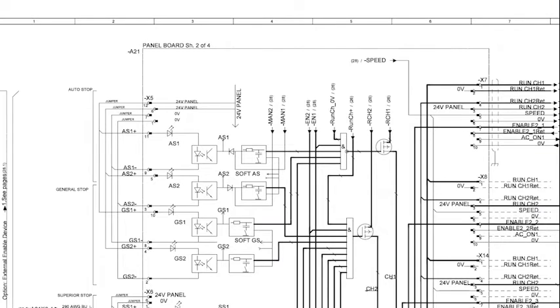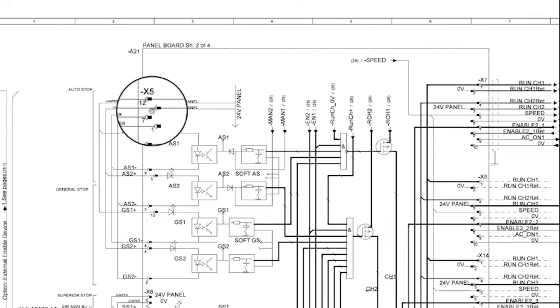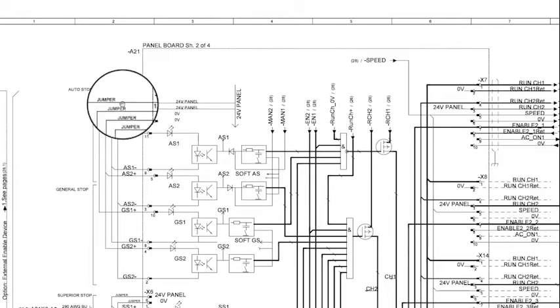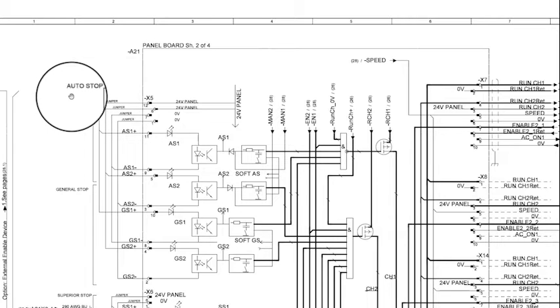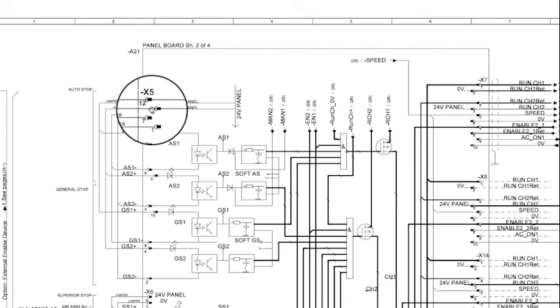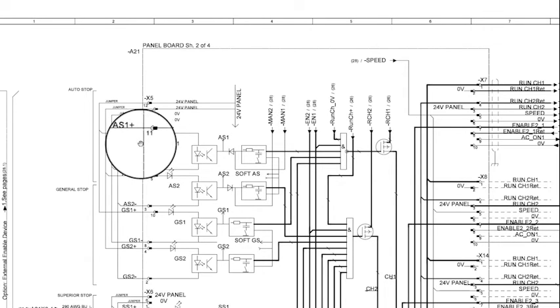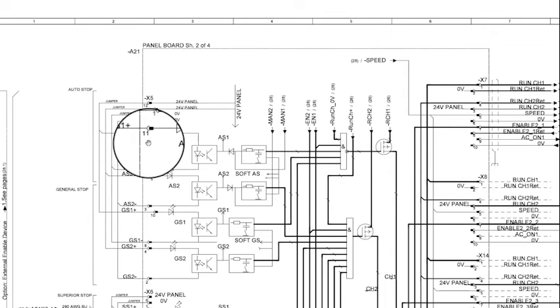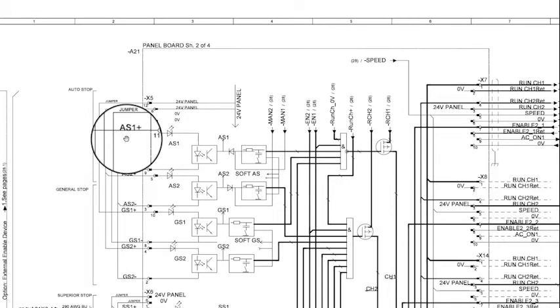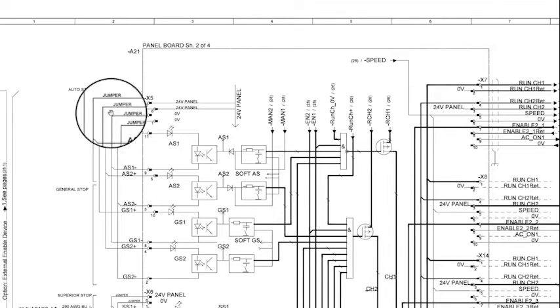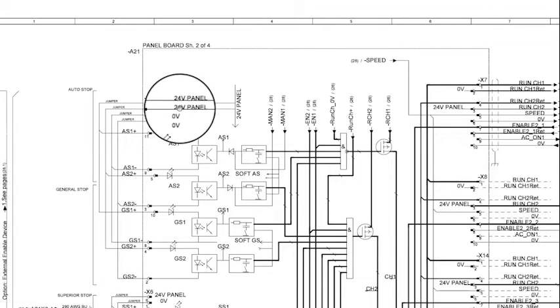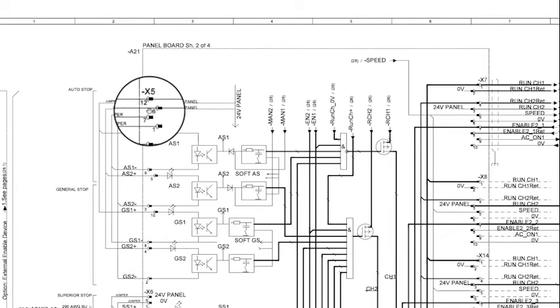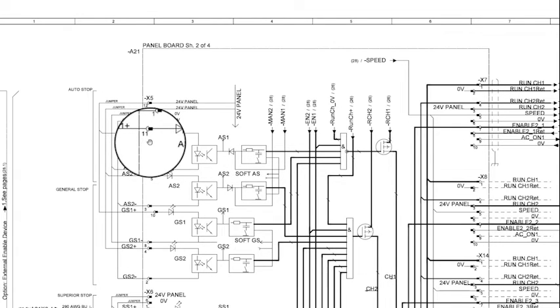Now that we are moving on to the circuit diagrams you can take a detailed look into what position within the X5 connector are designated for each of the auto stop channels. The X5 connector in position 11 is the first positive chain for auto stop circuit named AS1 positive. As you can see there is a 24 volt supply coming out of the panel board on connector X5 position 12 which is being pushed through the factory jumper to position 11 and 10.